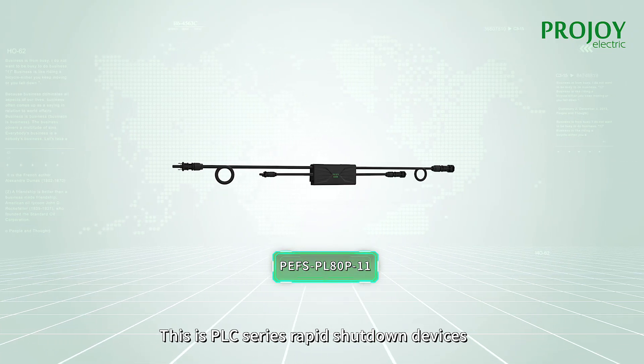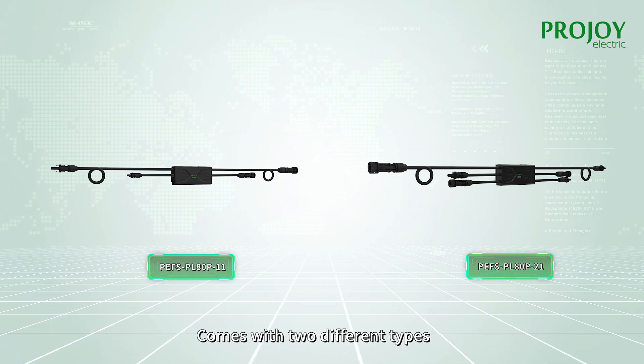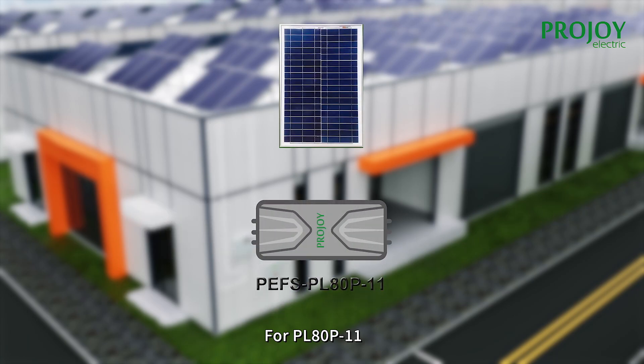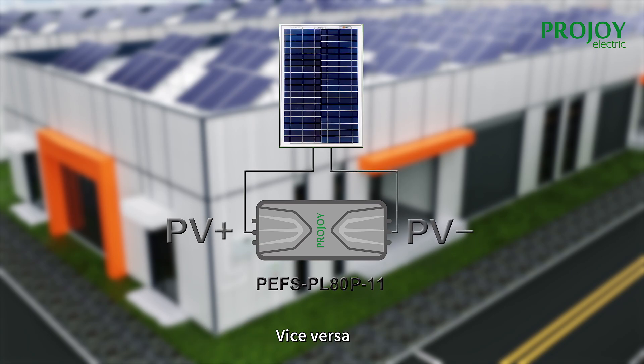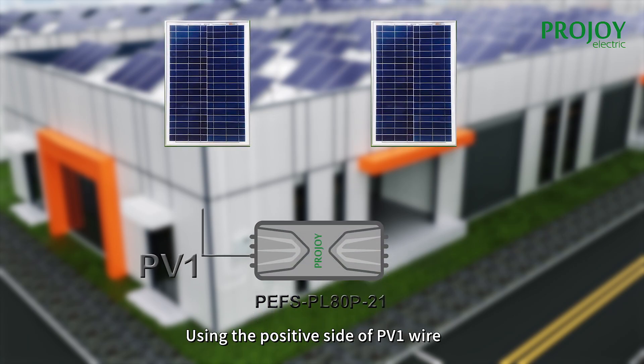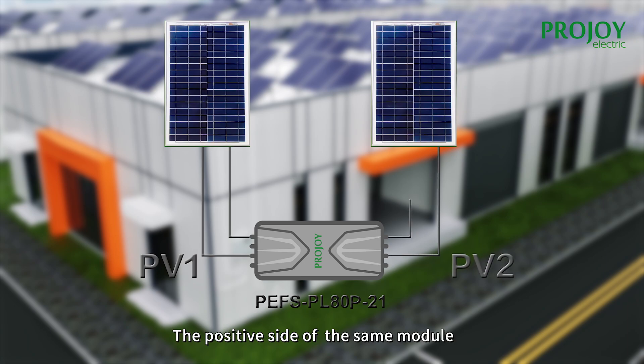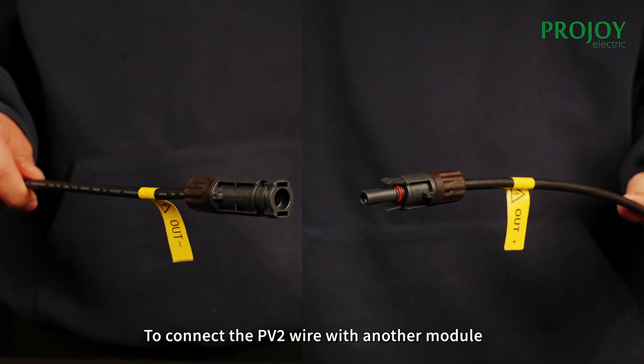This is the PL series rapid shutdown devices, which comes with 2 different types. For the PL80P 1-in-1, when connecting to modules, use the positive side to connect the positive side of the module wire, and vice versa. As for the PL80P 2-in-1 type, use the positive side of PV1 wire to connect the positive side of the module, and the PV1 negative connects the negative side of the same module.